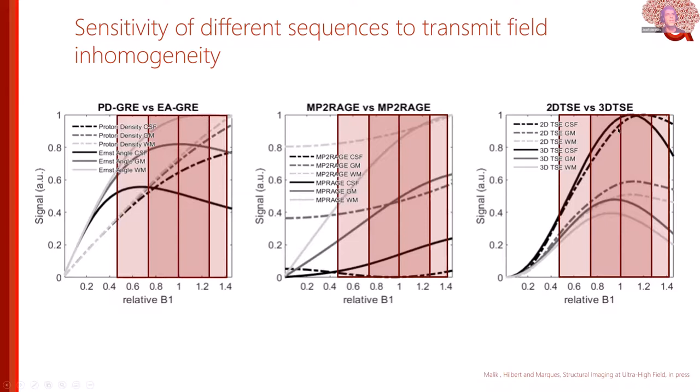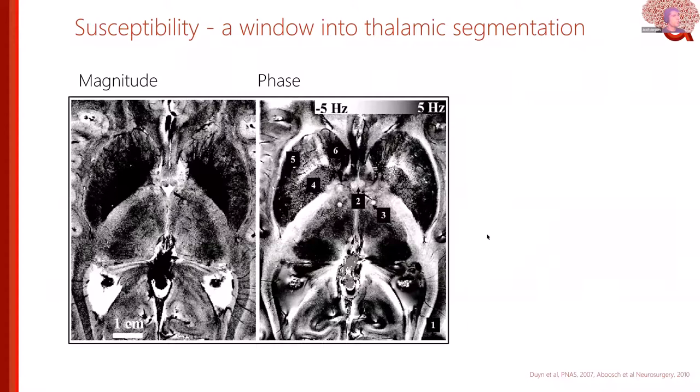The situation gets really bad for turbo spin echo sequences — 2D TSE or 3D TSE. They show a very large intensity variation that is not linear like in gradient echo but actually has a quadratic shape. In some cases you can have signal increases because of higher B1+, or even signal decreases, and we'll see the impact this has on thalamic imaging.